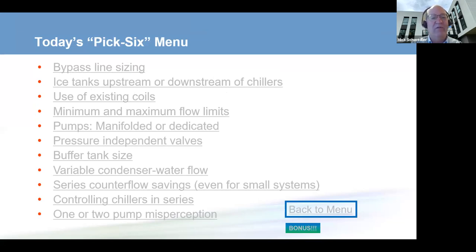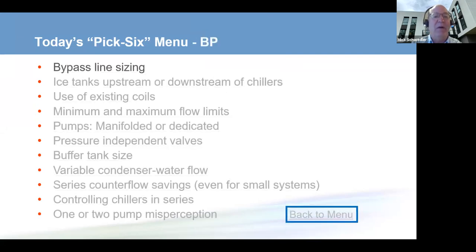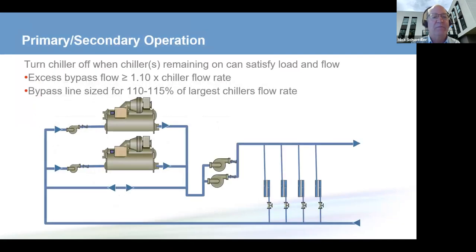Your local board of governors picks the 6. So if we want to do more in the future, we can pick a different 6. So we're going to start out with bypass line sizing, which was the first one that the board of governors picked. So we're going to talk about 2 different system types. First, a primary secondary system, and then a variable primary flow system.